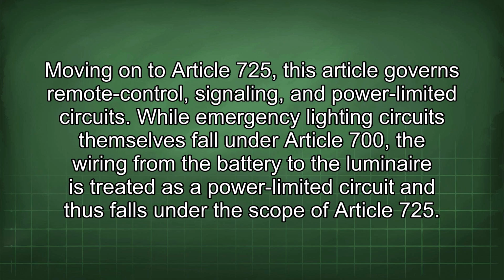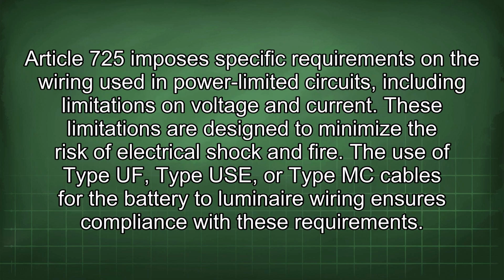Moving on to Article 725, this article governs remote control, signaling, and power-limited circuits. While emergency lighting circuits themselves fall under Article 700, the wiring from the battery to the luminaire is treated as a power-limited circuit and thus falls under the scope of Article 725. Article 725 imposes specific requirements on the wiring used in power-limited circuits, including limitations on voltage and current. These limitations are designed to minimize the risk of electrical shock and fire.